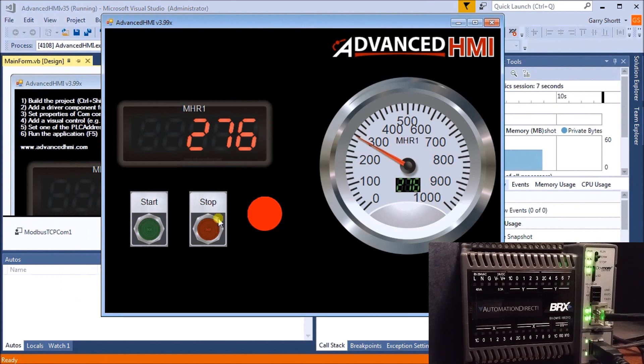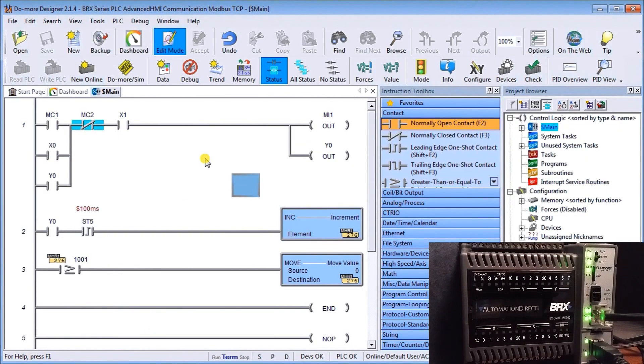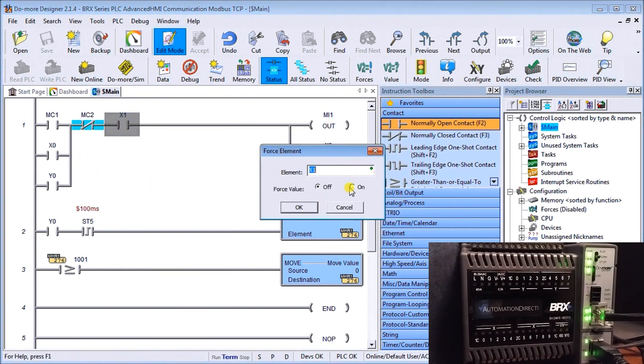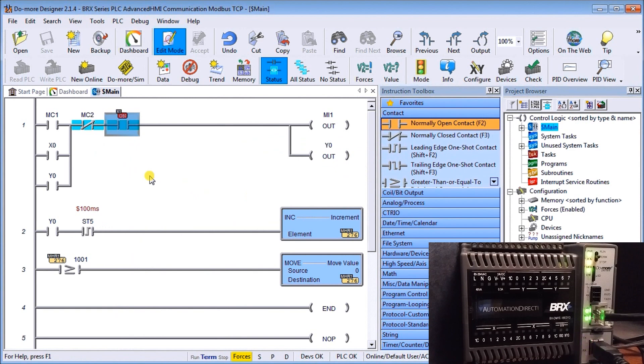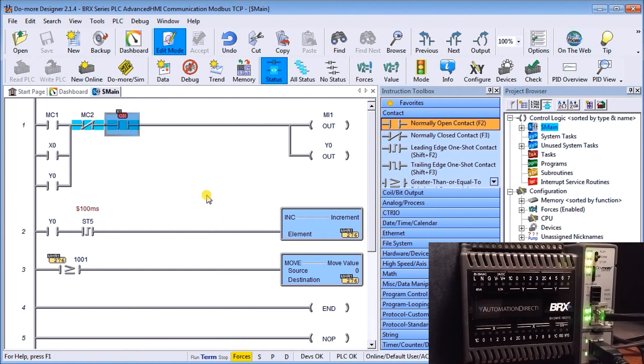Hitting Start or Stop, nothing happens yet because we haven't fully set things up. We go back to the ladder logic and force bit X1 on. Once that bit is forced on, the start/stop can function, MI1 turns on, which turns on our indication light, and Y0 energizes.